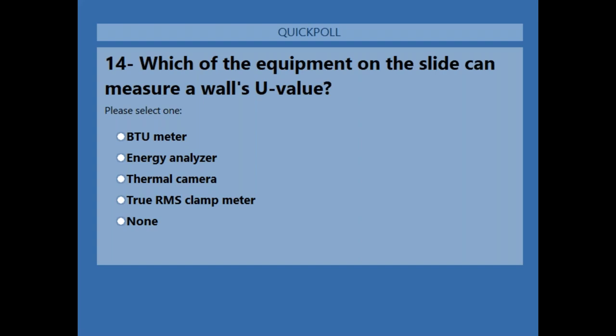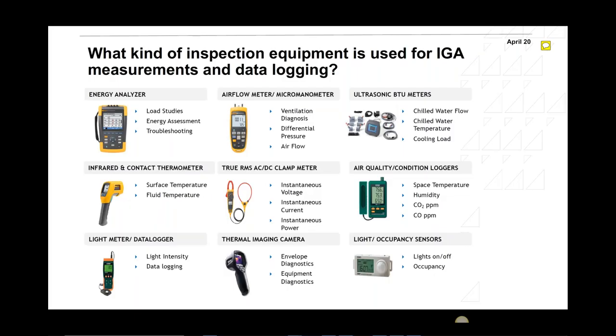Around 72% voted, and the right answer is none. Basically, none of the equipment shown here can give us the U value of a wall. What we would need is a heat flux meter. We need to install that for a long time, maybe 1 week, maybe 2 weeks, to check the heat flux within the wall along with the temperatures in and out, and then that would give us the U value of the wall or a roof. Normally we use it for walls or roofs.